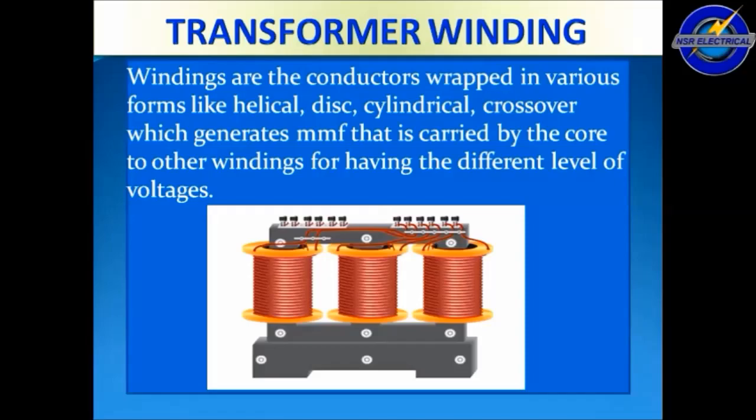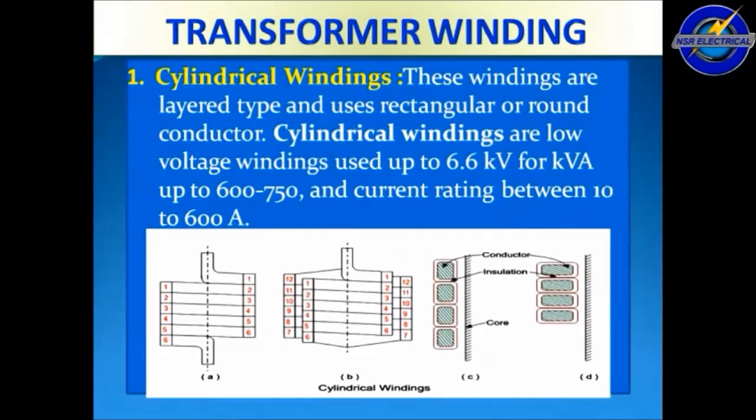This is the introduction part for basic purpose. Next we see the transformer winding types. The first one is cylindrical winding. These windings are layered type and use rectangular or round conductors. Cylindrical windings are low voltage windings used up to 6.6 kV, for kVA ratings up to 600 to 750, and current ratings between 10 to 600 amps.